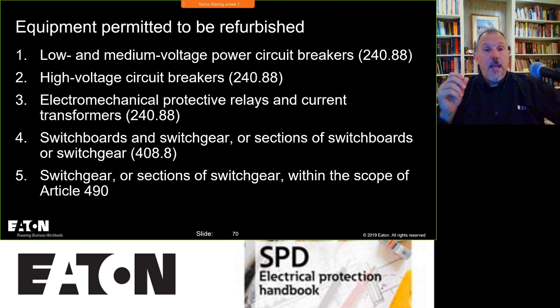Now, the AHJ is going to use the listing mark because in Article 90, remember that's the article we go dumpster diving for, that'll tell you they're going to have to approve it, and they're going to have to look for something. If you've built something or modified a product and you're installing it, they're going to look at it and say, what gives me the level of confidence that it's going to do what it's supposed to do? They usually look for the listing mark, and if it's got a listing mark, they're good. If it doesn't have a listing mark, they're not going to want to crawl out on that limb too far, right? Unless they really love you. You want to limit their crawling out on that limb by getting some sort of listing mark or third-party review of what you're doing.